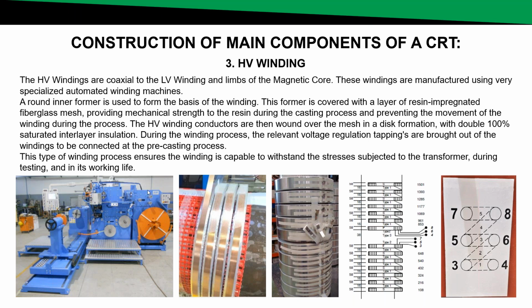So if you look at the photo, there's a typical winding machine that is used to wind HV windings. There is the round former with a resin mesh around it, with the HV conductor being wound on top of the mesh. Then there's a typical example of a completed HV winding where you can see the relevant tappings coming out. There's a nice schematic diagram showing the typical construction of a high voltage winding. And then the last picture shows you some tapping positions and how the tappings are orientated on a high voltage cast resin transformer winding.